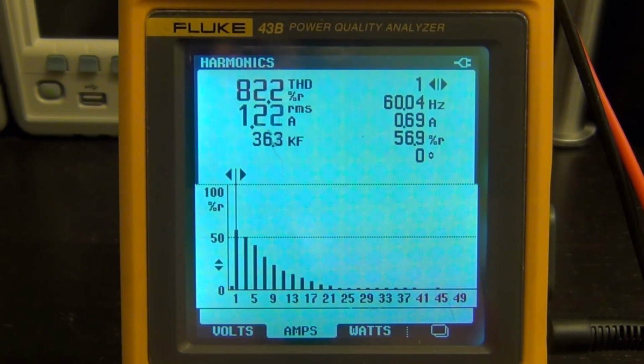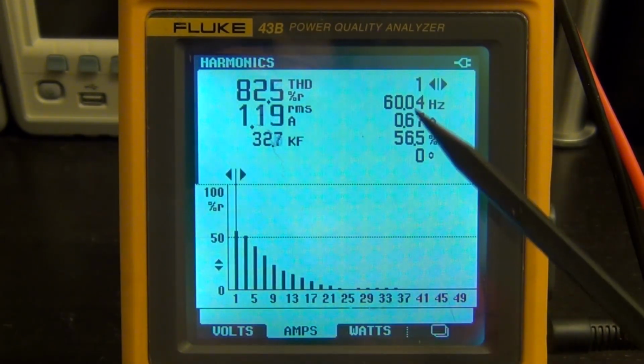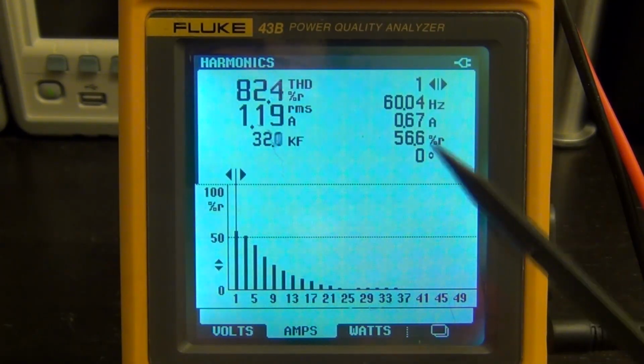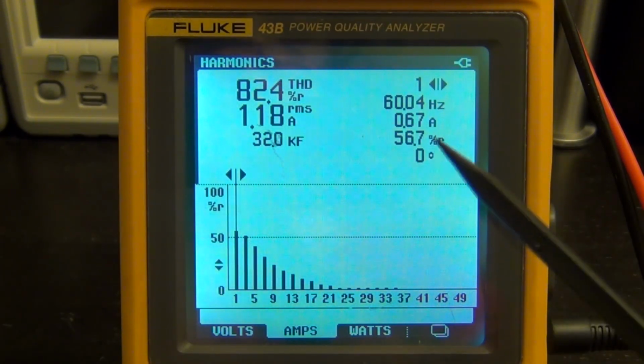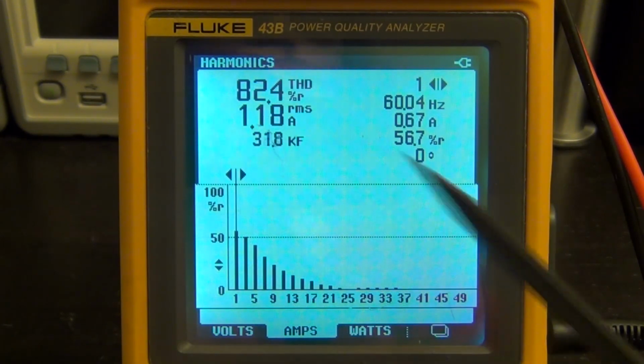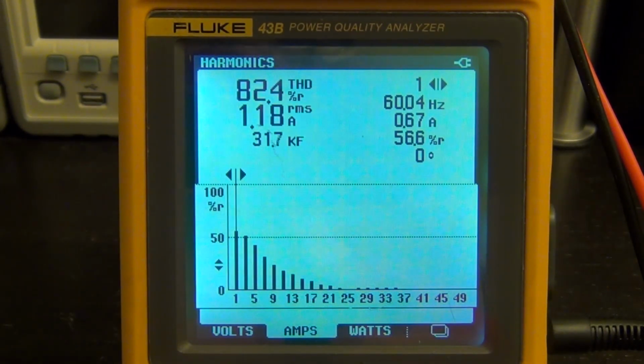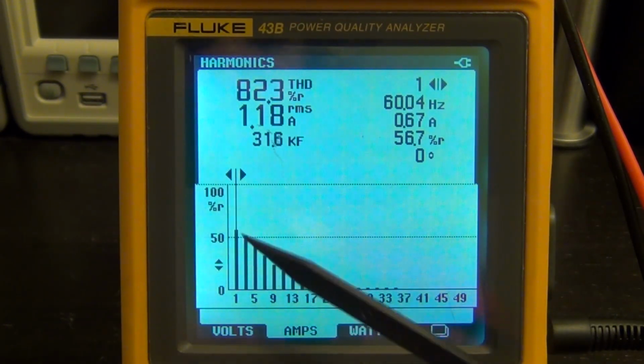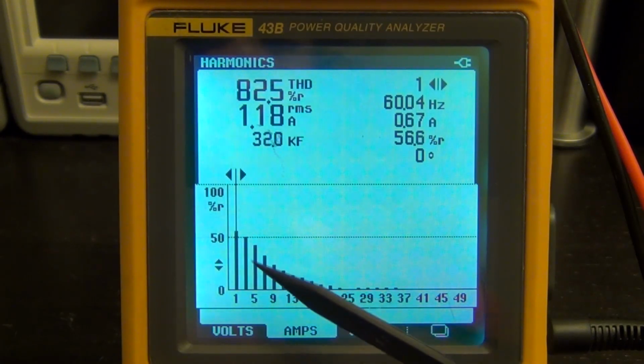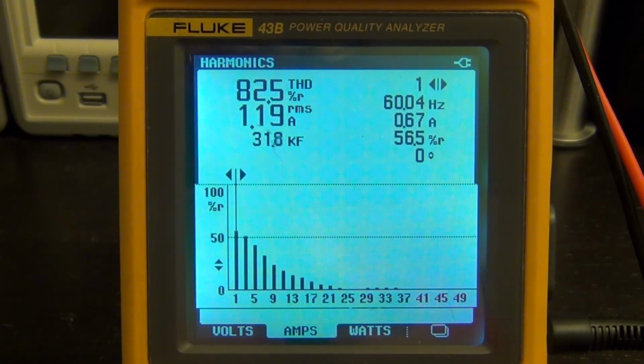And here, in the next screen, is going to tell us exactly the frequency content of all the harmonics that go into the current measurement. And check it out, the fundamental tone being at 60 Hertz, right over here, you can see that it has almost all the current in it, 0.67 amps. But check it out, the THD is 82.4%. That's horrible. And you can see the relative power of all the harmonics. And it goes all the way out to the 21st harmonic over there.